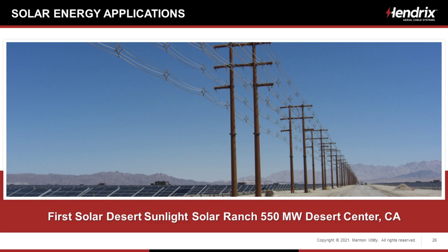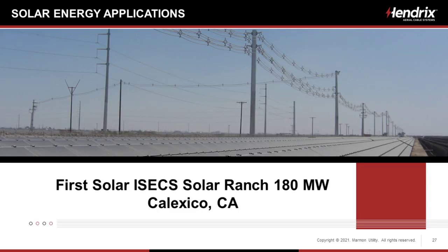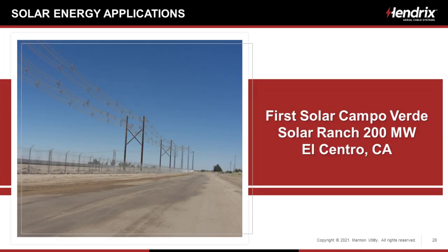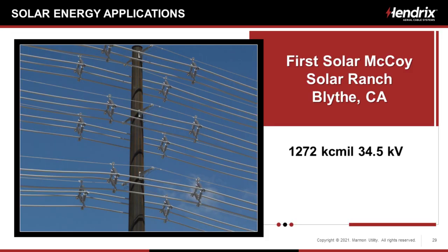Going back to Desert Sunlight, this is getting closer to the sub, but before we divided it up into two poles so we could enter the substation more easily. Here we've got 9 circuits on one pole line. So that's 450 megawatts there on one pole line. And we've done a bunch of other projects with First Solar. This is ISECS in the Imperial Valley. That's 180 megs. We got that on four collection circuits. Close by to that, we have First Solar Campo Verde in El Centro, and that's 200 megawatts we got on 4 circuits.